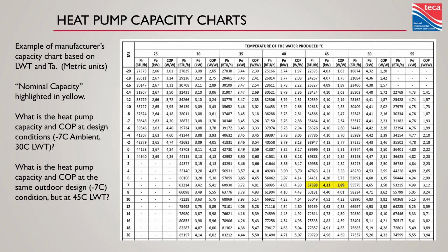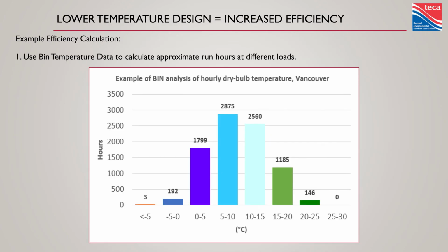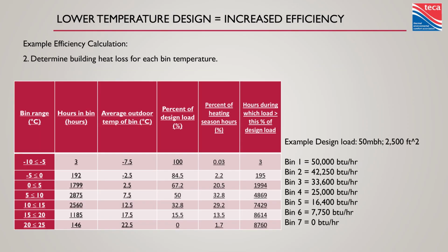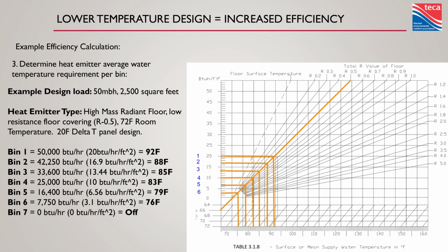But let's say we take that heat pump and put it into a house. We've got a bin temperature chart, we already covered that. So let's start figuring out how we heat that space. Let's say it's 50,000 BTUs, 2,500 square feet. We can look at all these different temperature bins and figure out just how many BTUs we're going to need for each one of those bins. And we can pop over to a heat output chart for radiant floors, and we can see for each one of those bins, what water temperature do I need? So now, bin 1, the coldest time, our design load, needs 92 degree water.